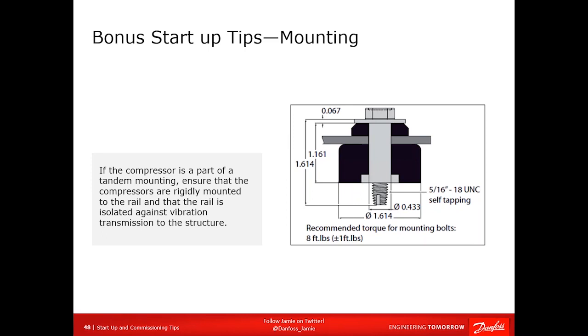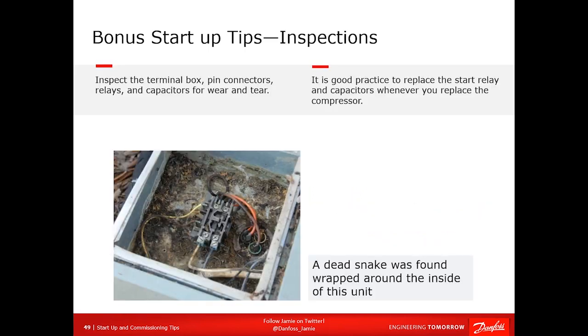On some of the tandem systems in Danfoss, you'll actually see a bracket between the two compressors. I lost the oil charge on a job because of this, when it was installed incorrectly, and we ruined a roof. It got very expensive, all right? So take it from me, this can cause a lot of problems down the road, and you don't want to overlook it. Finally, check the contactor, the wiring, and the capacitors.